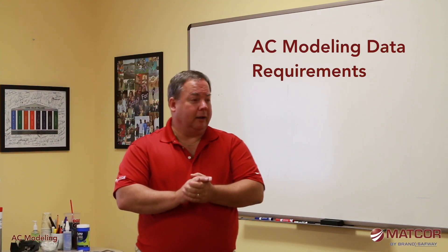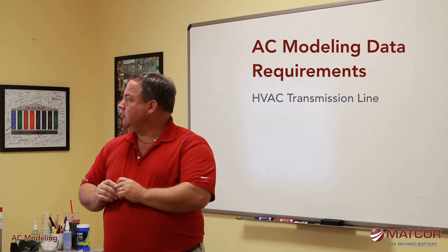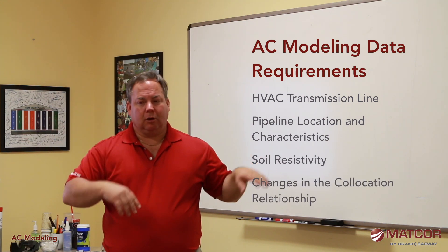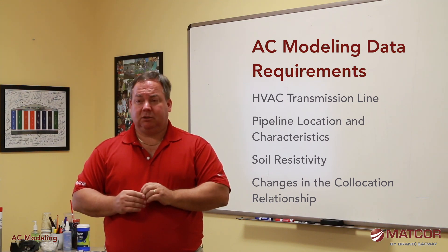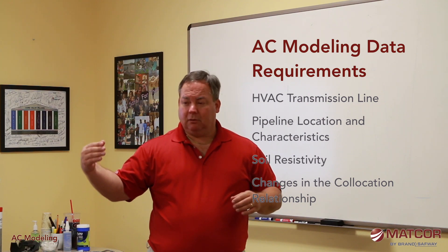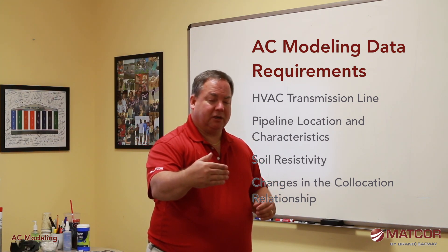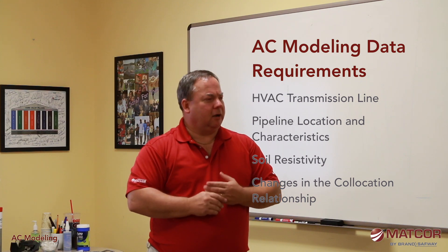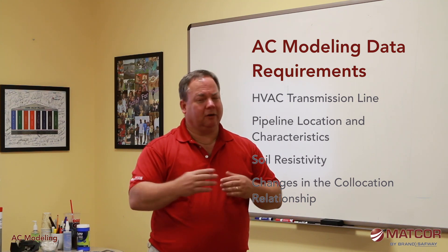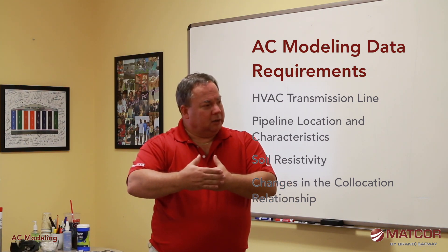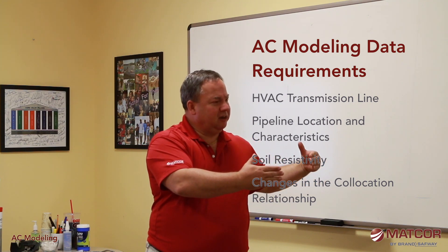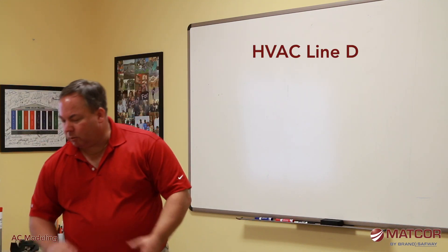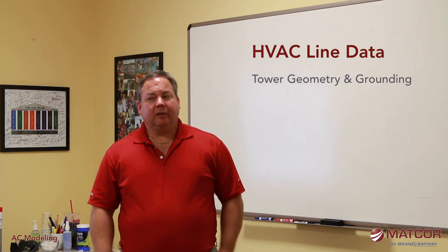We need a lot of data to fill the model. We need data on the HVAC transmission line, the pipeline, soil resistivity, and we need to know where changes occur — these are called excitation points. As the pipeline moves along, if there's a sudden change in the pipeline or the high voltage tower line, that becomes an inflection point. If the pipeline and HVAC line run parallel for a long distance and then suddenly deviate, that's where problems will likely occur.